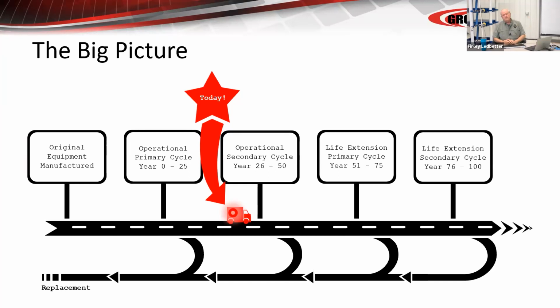So we really don't have a suitable replacement for the vacuum breaker today. So you're going to be stuck with it for the foreseeable future. It's already 50 years old. I can see 50 more, so 25 years to 100 years. So we've got to be able to keep this equipment in service 100 years. So the decisions you make today for your owners, for your customers, need to be: how do we keep this equipment that was designed to operate 20 years in service for 100 years?